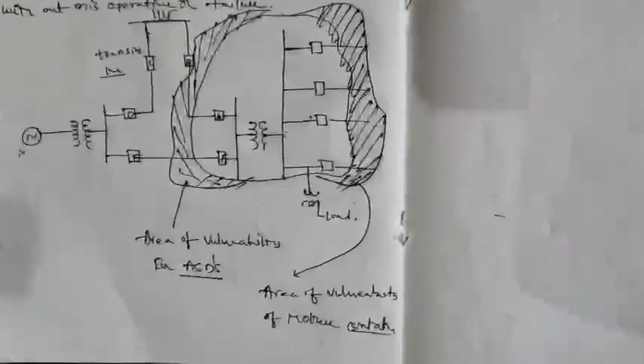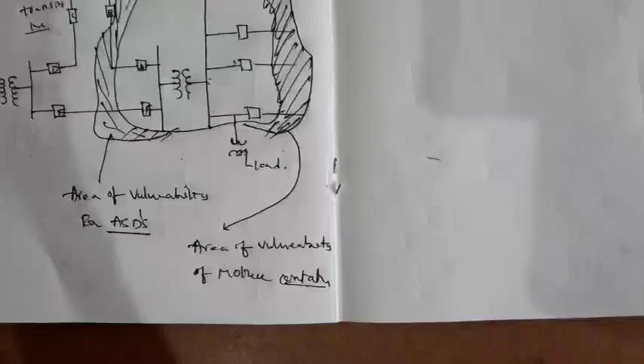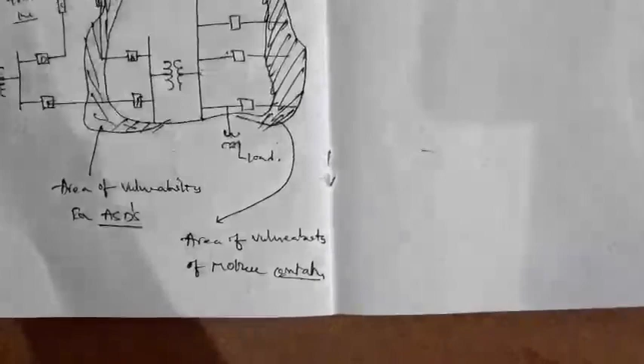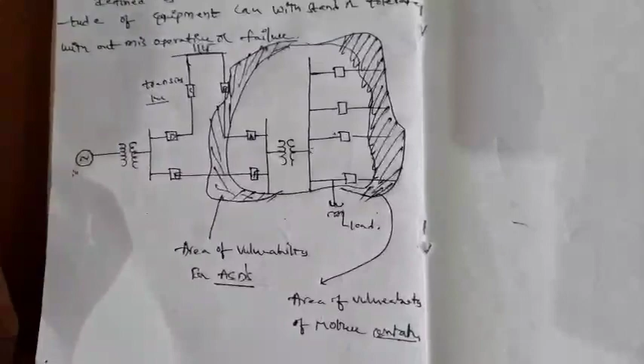That means during this area the equipment can withstand. So this is one example of a vulnerability diagram for motor contactors and adjustable speed drives served from the distribution system. The load is subjected to faults, so voltage sags can happen. The load will be subjected to faults on the transmission system and the distribution system. The number of voltage sags that a facility experiences can be determined by combining the area of transmission and distribution performance faults.